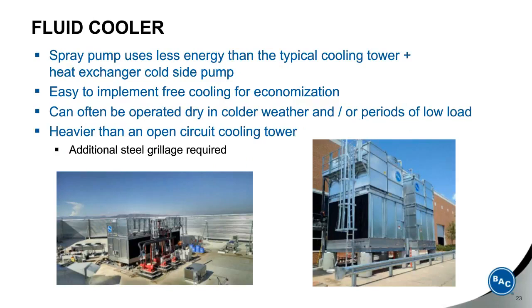Now, the spray pump that recirculates the water from the cold water basin up to the spray system of the tower uses less energy than the typical cooling tower heat exchanger cold side pump. It is also easier to implement free cooling for economization in a fluid cooler system because of the less need for piping complexity. And you can often operate the fluid cooler dry in colder weather and or periods of low load. This allows you to either save water or minimize icing issues during very cold weather operation.